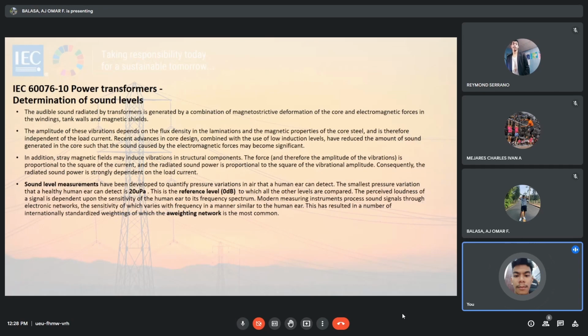Dito sa IEC 60076-10, determination of sound levels ng mga power transformers. The audible sound radiated by transformers is generated by a combination of magnetostrictive deformation of the core and electromagnetic force in the windings, tank walls, and magnetic shields. The amplitude of these vibrations depends on the flux density in the laminations and the magnetic properties of the core steel, and it is therefore independent of the load current.